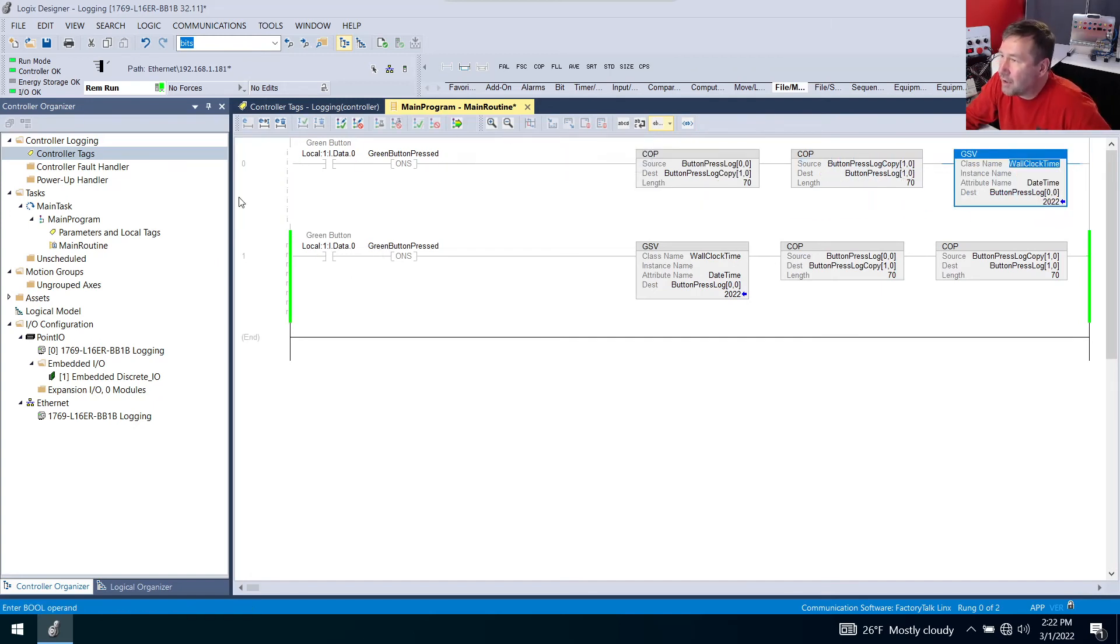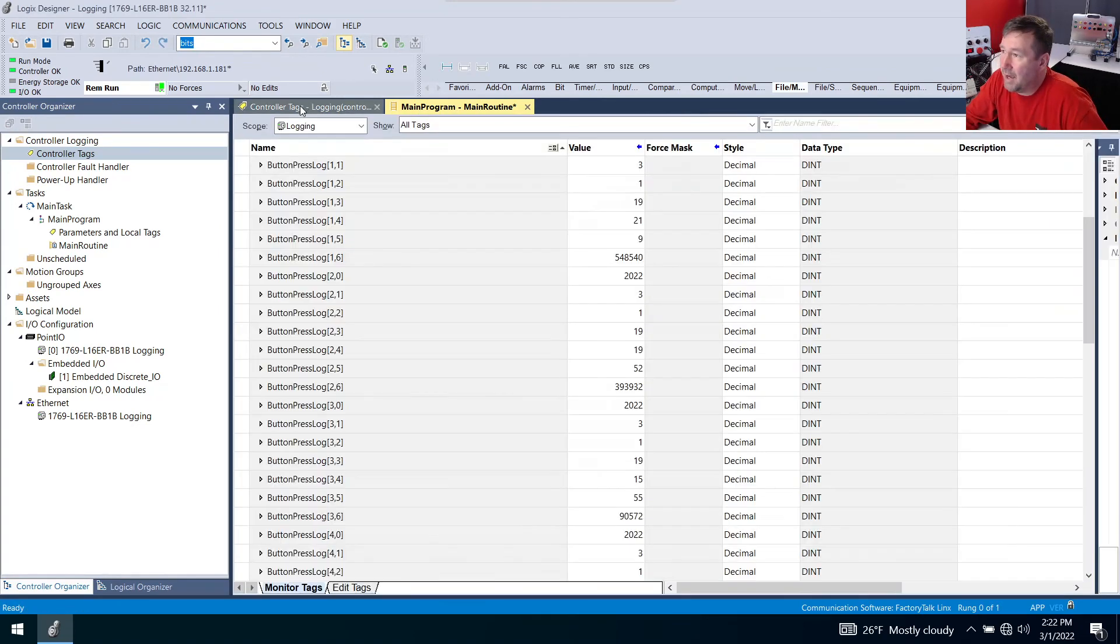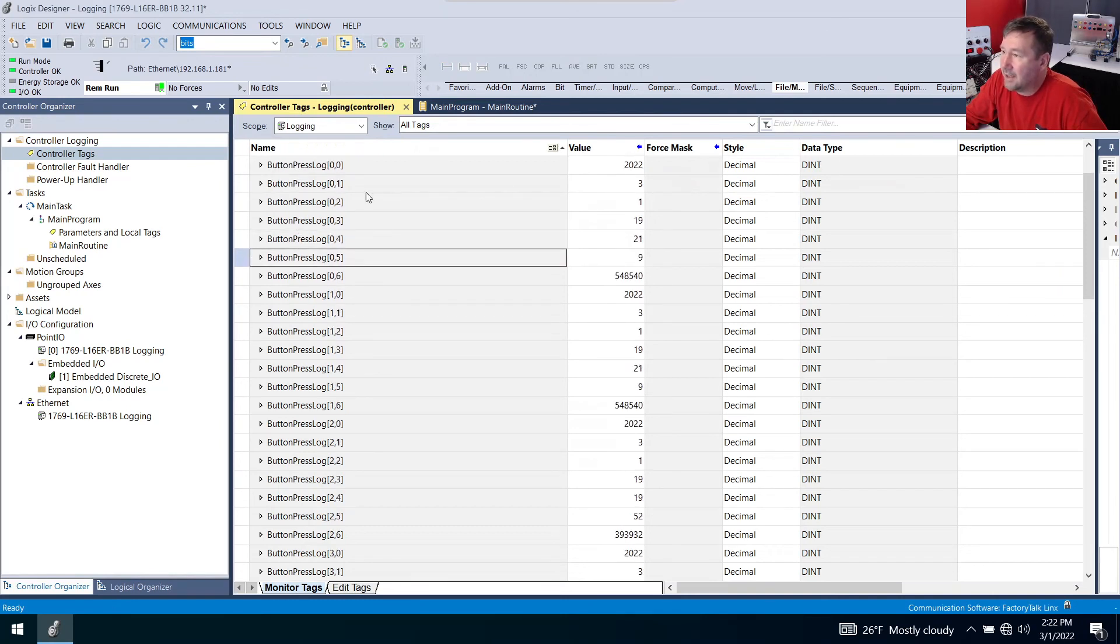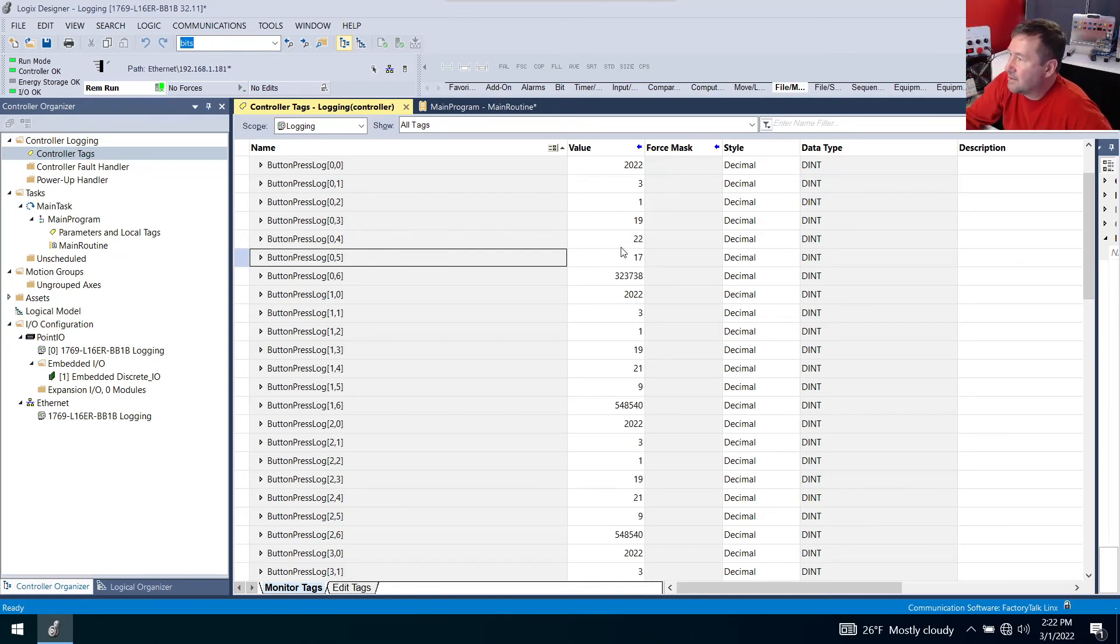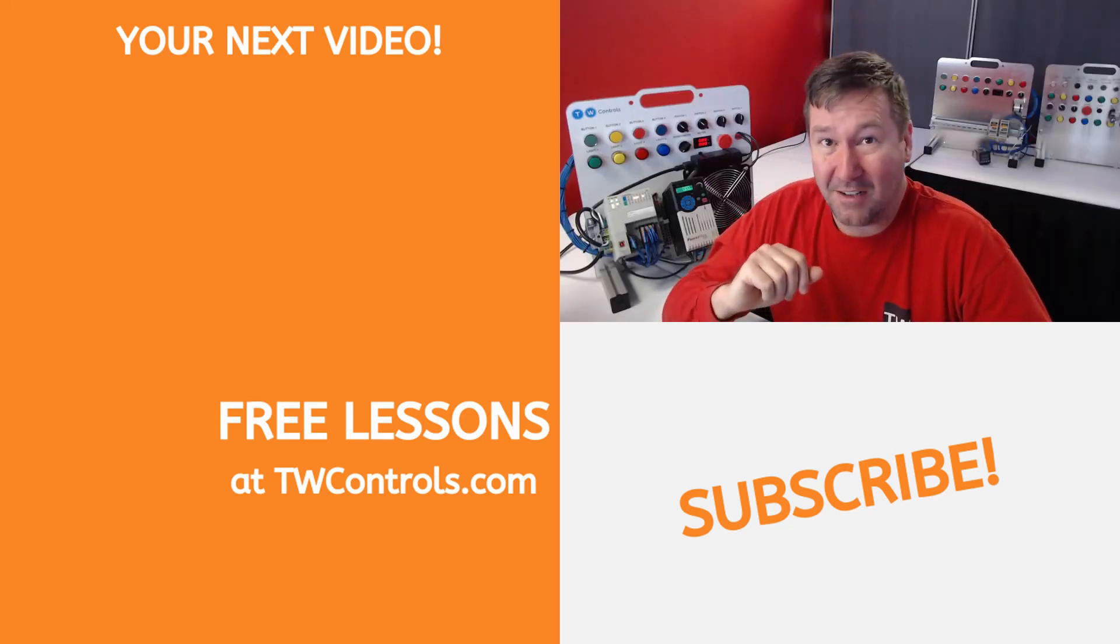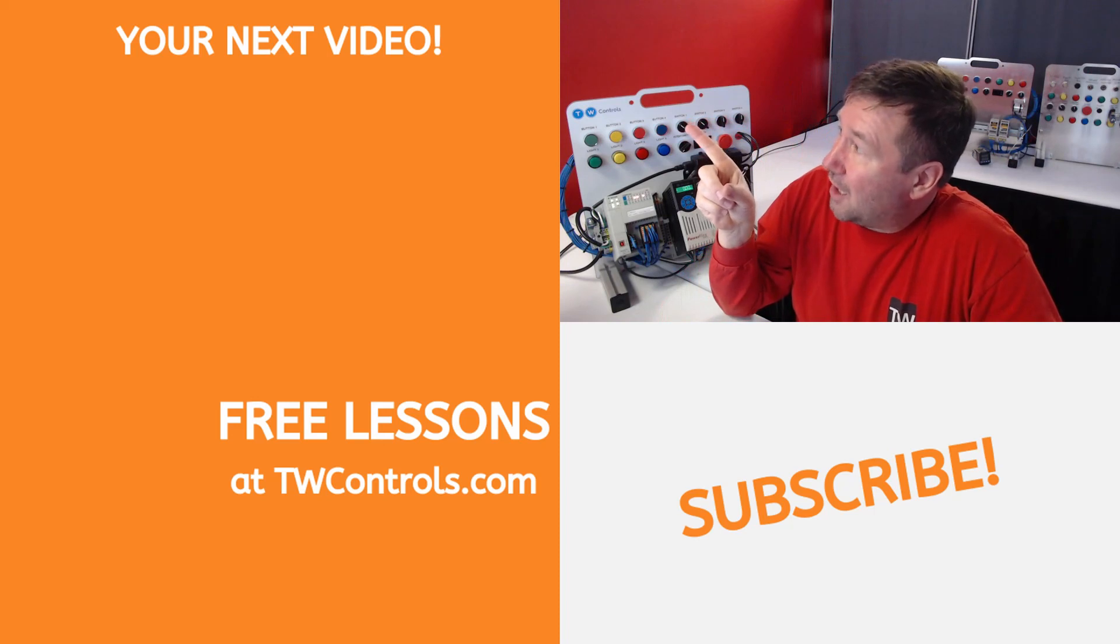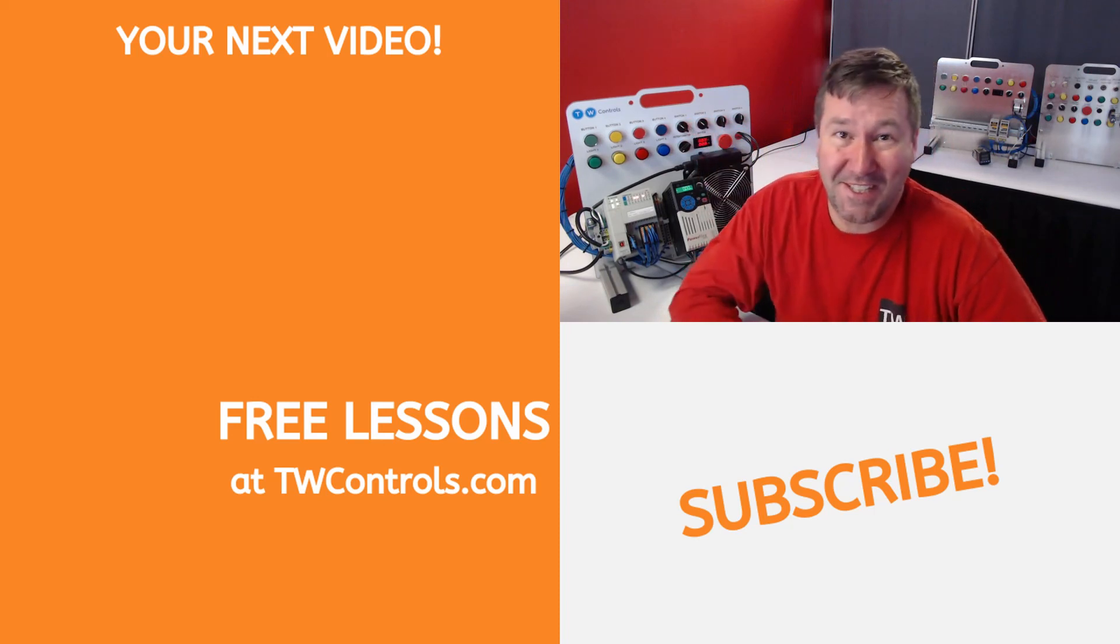Let's go back to our controller tags and we're going to look at elements three, four, and five again. So this time I'm going to press the button and we're at 19, 22, 17. Now notice that's not the same time as this one. So let's press it again. So you see that 19, 22, and 17 are going to come here now. And now I'm going to press it again and you're going to see it comes into element number two here. So now we're getting a shift like we want. But that's only one way to do data logging. Click here for a playlist of other ways to use data logging to troubleshoot your machines.